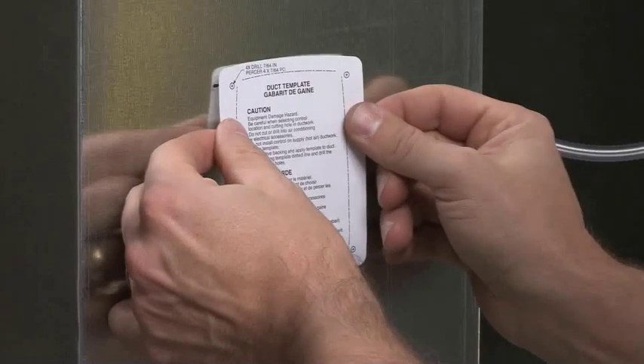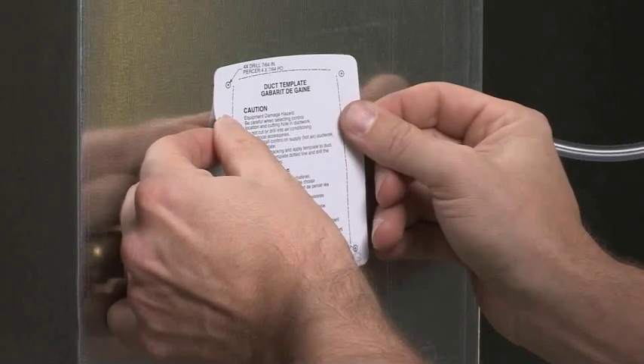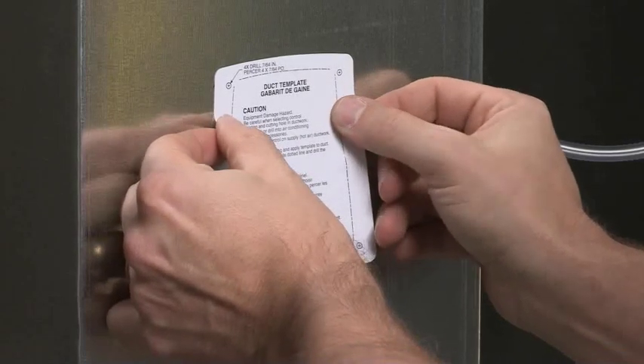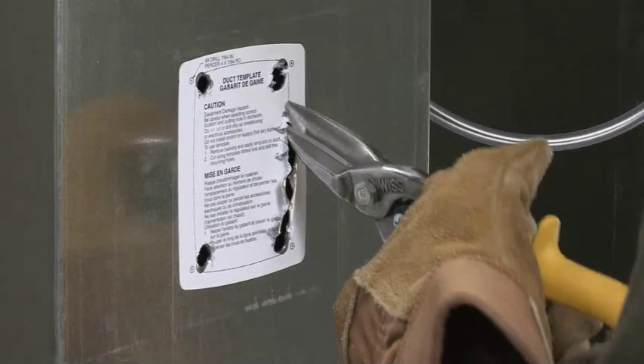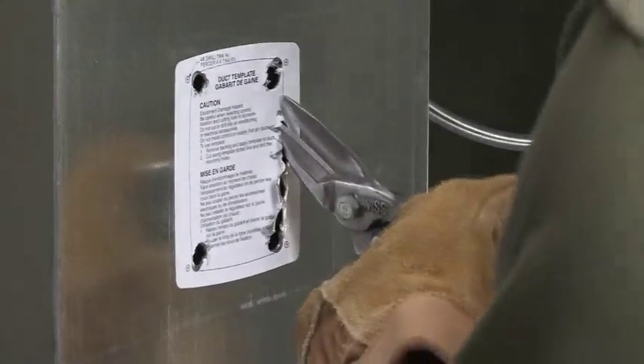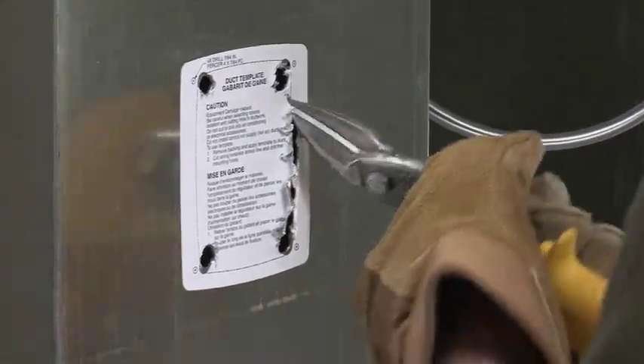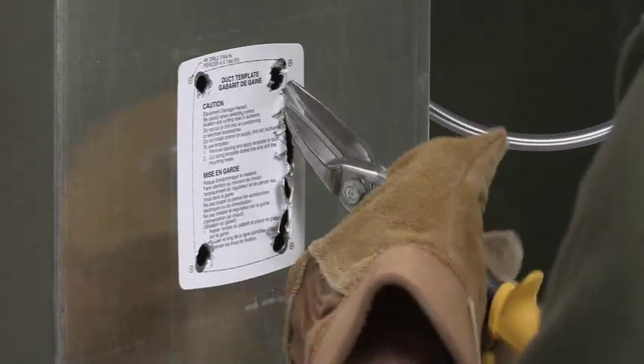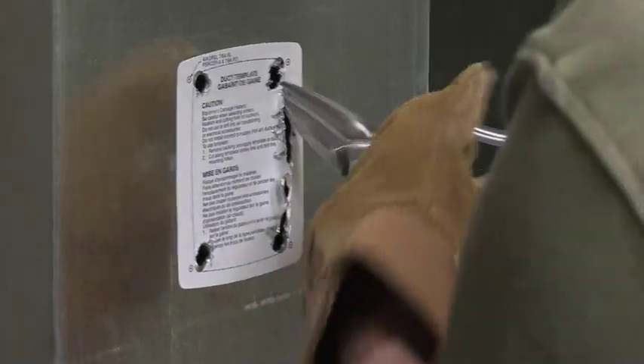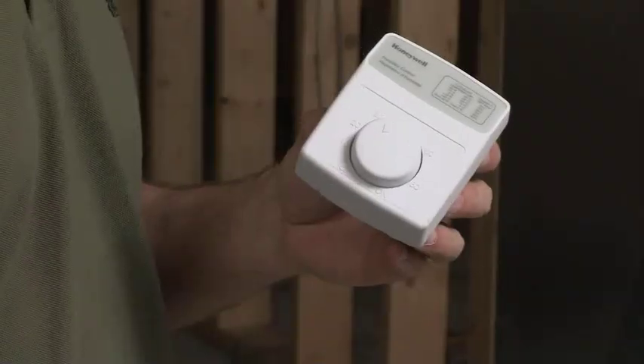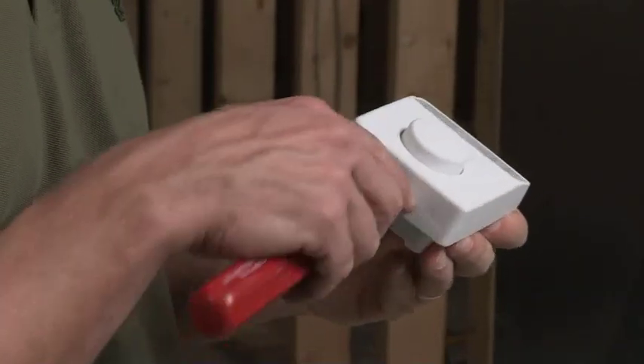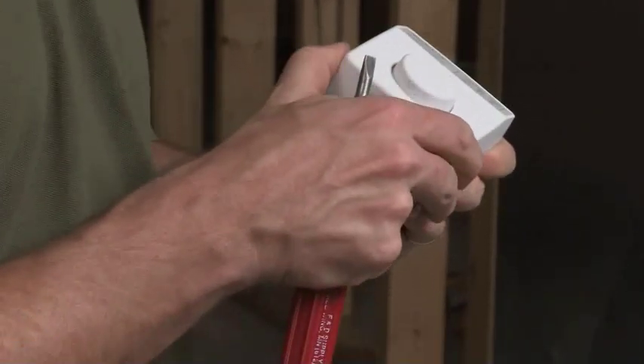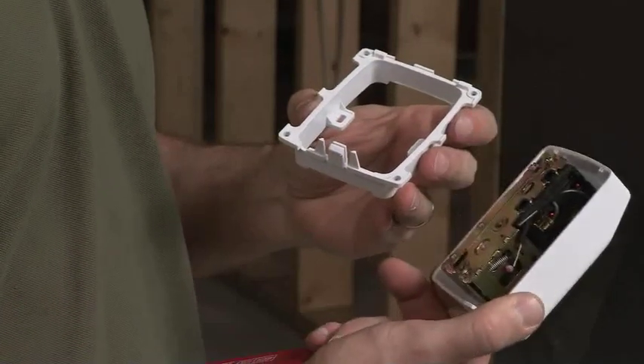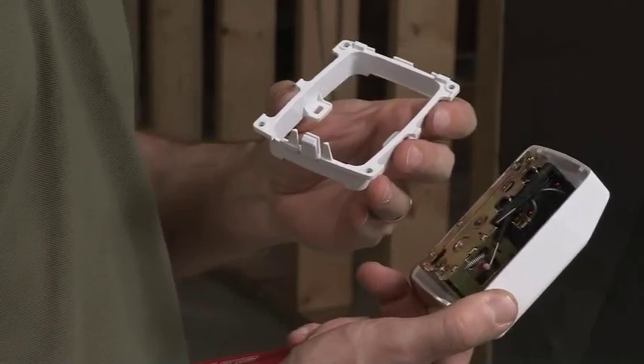You'll want to mount the humidistat to the ductwork at least 8 inches upstream from the humidifier, so that it can correctly sense the relative humidity in the home. Place the template on the location you've chosen. Once you level the template, cut along the dotted line of the template with metal shears or tin snips. Next, remove the base bracket from the humidistat by inserting a flathead screwdriver into the case removal slot and separating the two pieces.